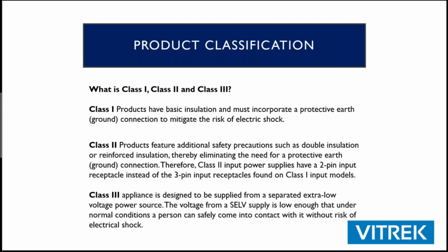It's typically going to have, here in North America, a NEMA 5-15 power cord on it. You're going to have a line, a neutral, and then a redundant ground. That ground is going to be connected to the metal chassis of the product, and that is going to keep you isolated from line and neutral, and also protected by shunting any current to ground, not through the operator, who's going to have a little bit higher resistance, or I should say a lot higher resistance, than that path to ground.